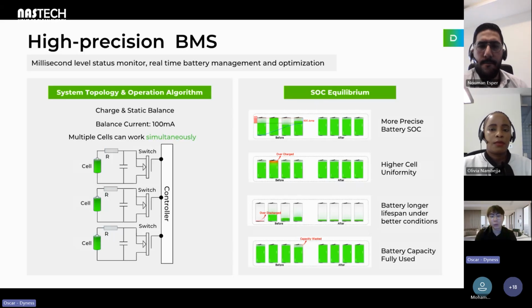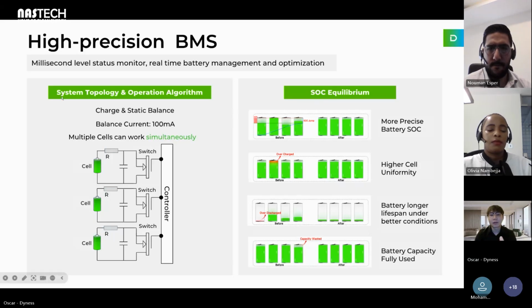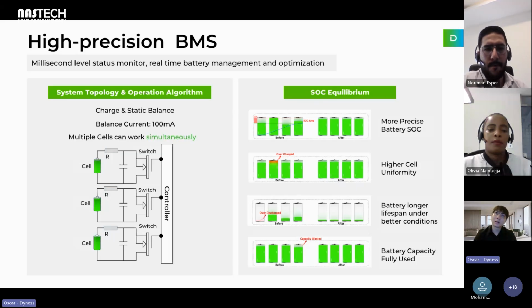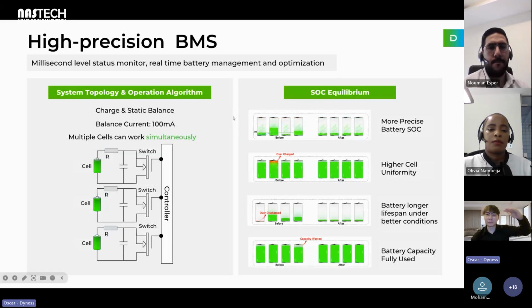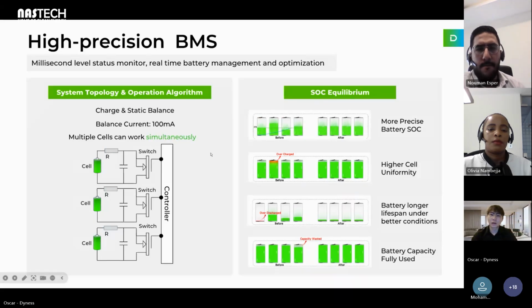This is what we have in the BMS. We have passive balancing to control all the voltages at the same level for all battery cells. When there is a difference between battery cells, and it exceeds, for example, 30 millivolts, it will trigger the passive balancing, and the higher SOC will stop charging and wait for the others to charge together.